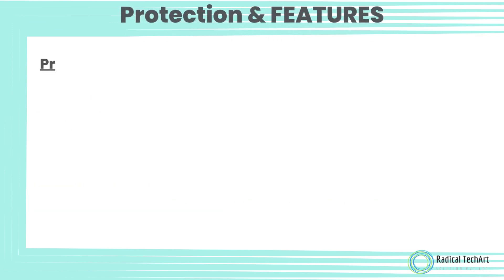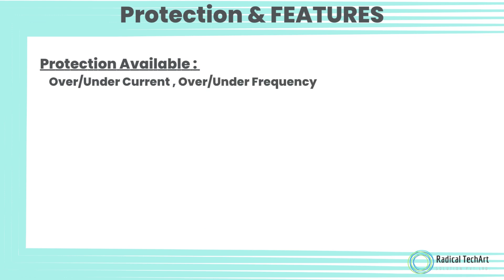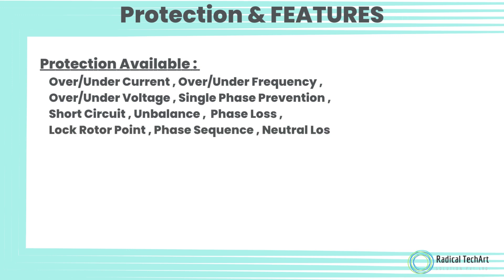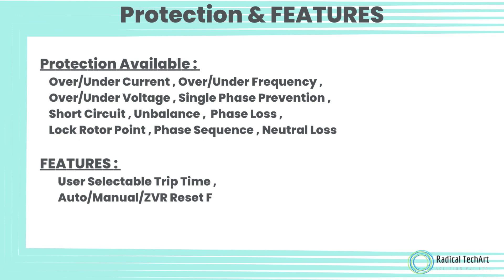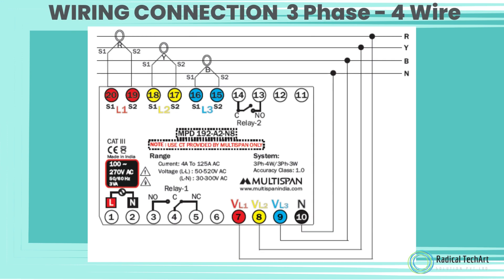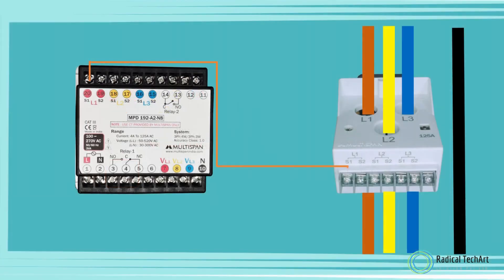Protection available: Over/Under Current, Over/Under Frequency, Over/Under Voltage, Single Phase Prevention, Short Circuit, Unbalance, Phase Loss, Lock Rotor Point, Phase Sequence, Neutral Loss. Features include user-selectable trip time, Auto/Manual ZVR Reset Function, True RMS Measurement. Wiring connection supports 3-Phase 3-Wire and 3-Phase 4-Wire configurations.